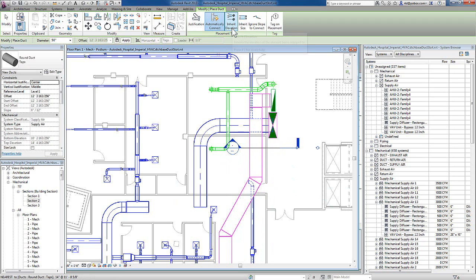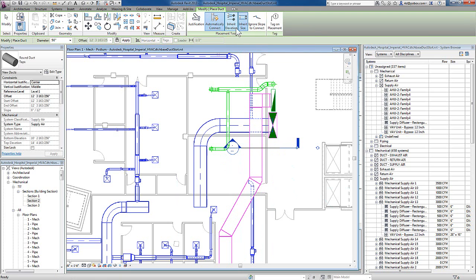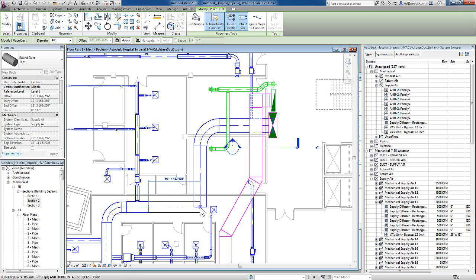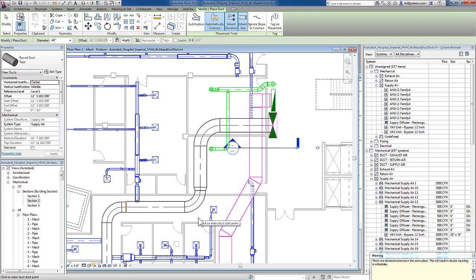I also can choose to inherit size and elevations from existing ducts. So if I choose to inherit size and elevation, I can pick the duct. And as I pick end points in the connectors, Revit will automatically add both the transitions as well as the corner conditions.